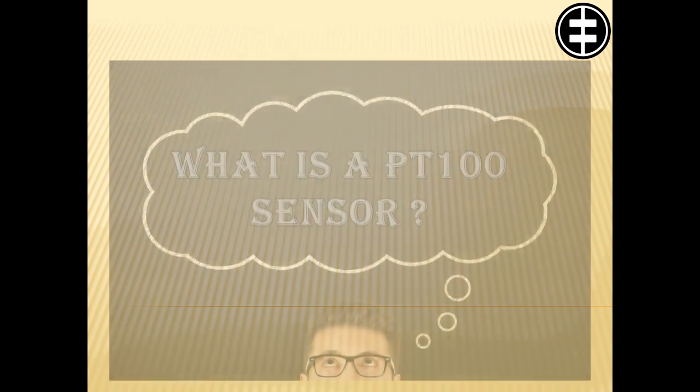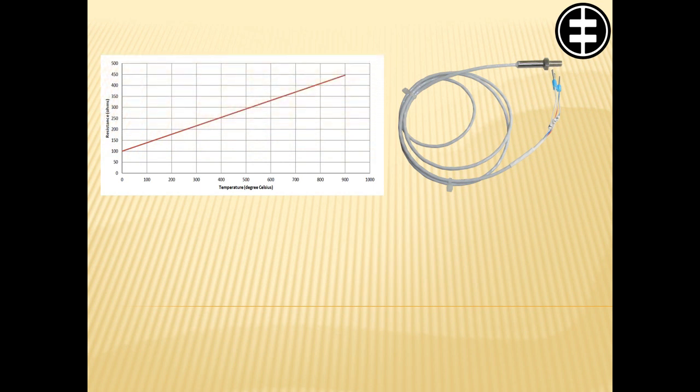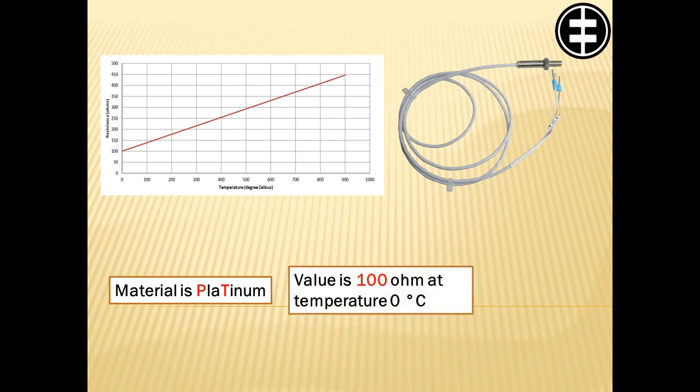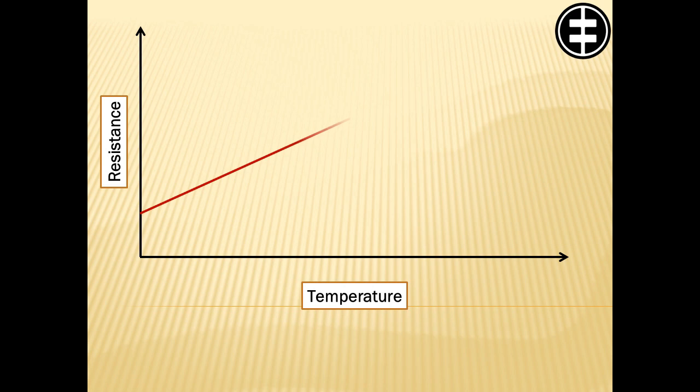What is a PT100 sensor? The PT100 is a sensor based on resistance measurement principle. Material is platinum and resistance value is 100 Ohm at temperature 0 degrees Celsius. Platinum has a positive resistance temperature factor, resistance increases with rising temperature.